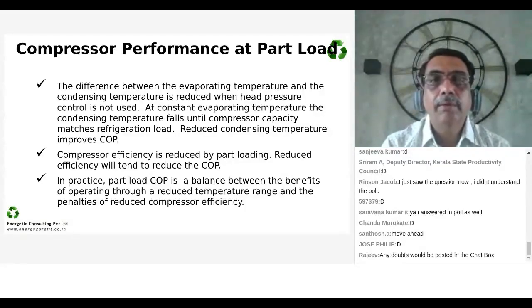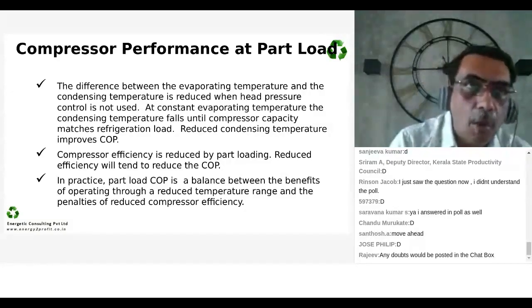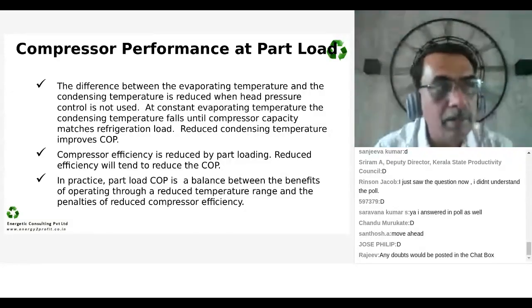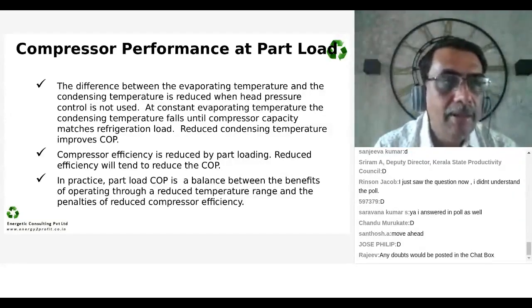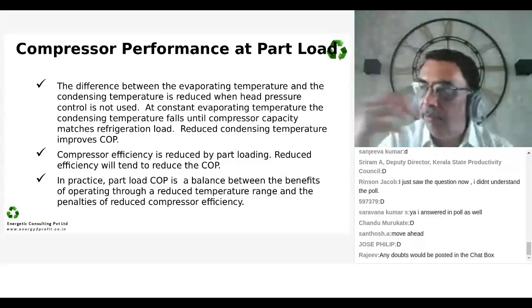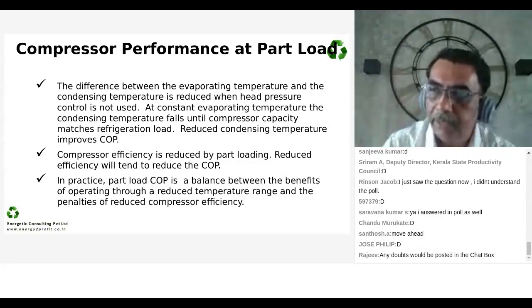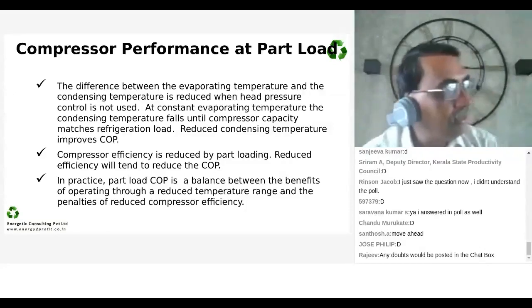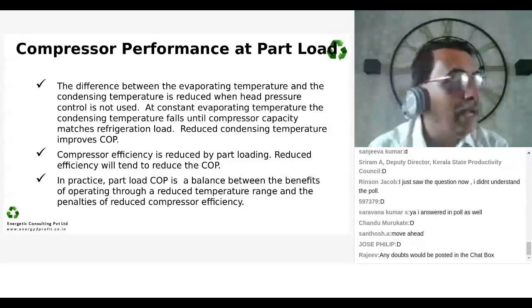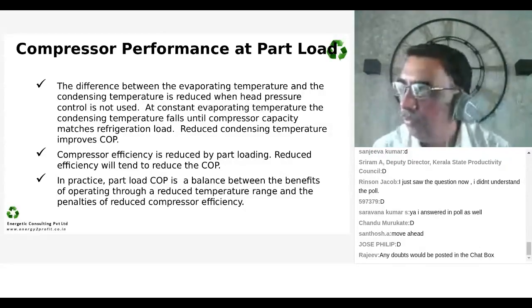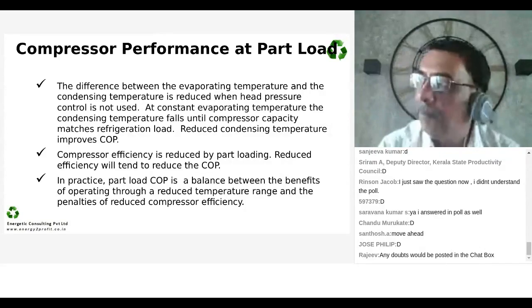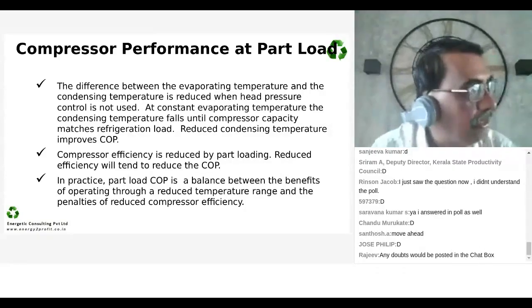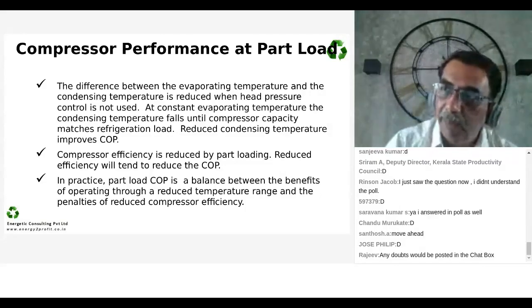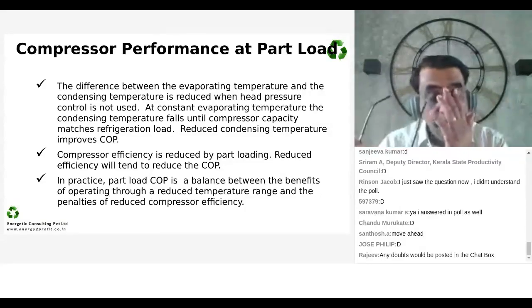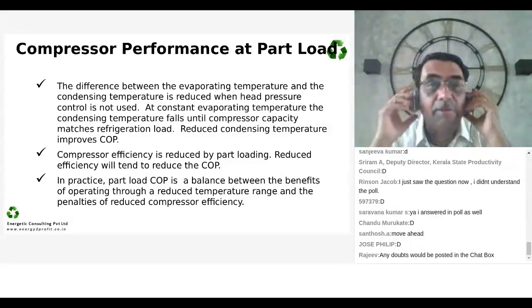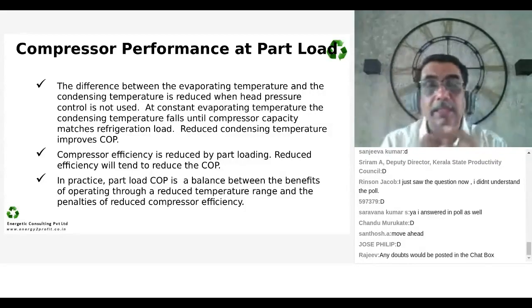Now, the part load performance is compromised because the displacement of the compressor is constant. However, the volume of refrigerant vapor coming from the evaporator to the compressor is low, which means that the compressor is starving for gas. Obviously, the whole system is designed for 100 people to sit in a restaurant, and you have only 5 or 6 people sitting in. So you do not have adequate heat load, which means that the refrigerant is not evaporating and giving cooling to the space. When there is no evaporation of refrigerant, the compressor is starving.